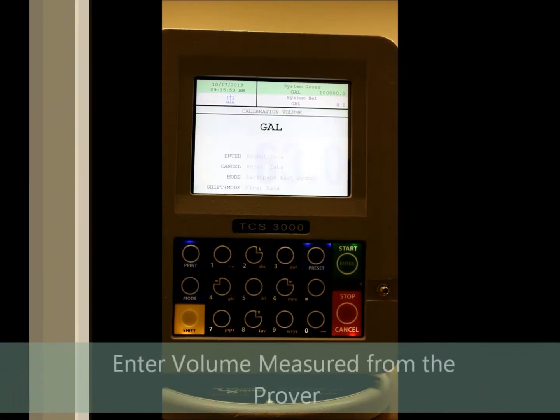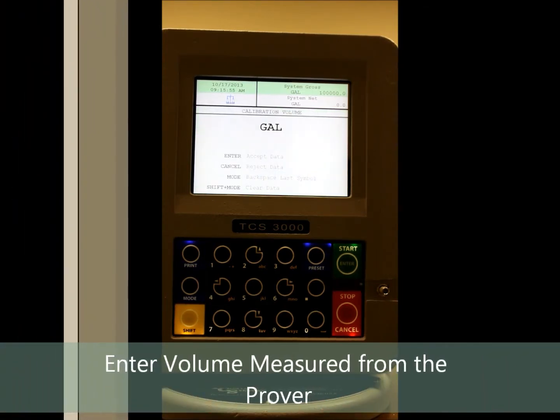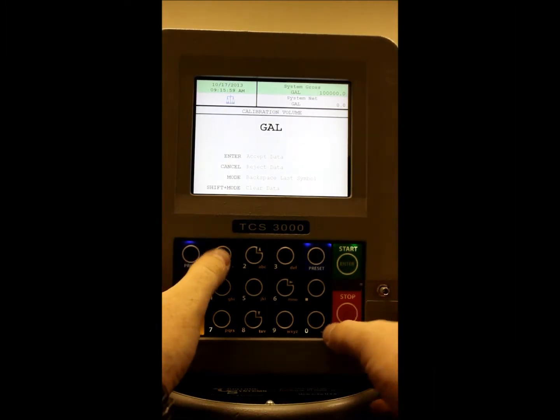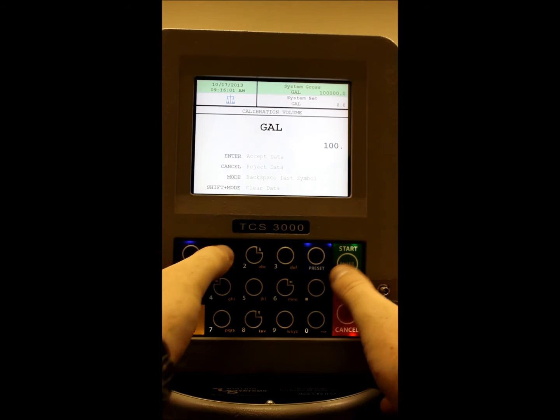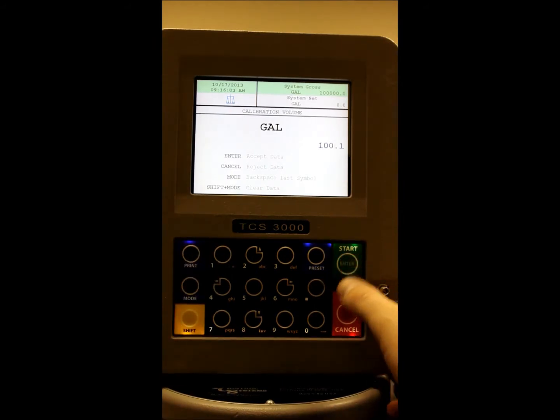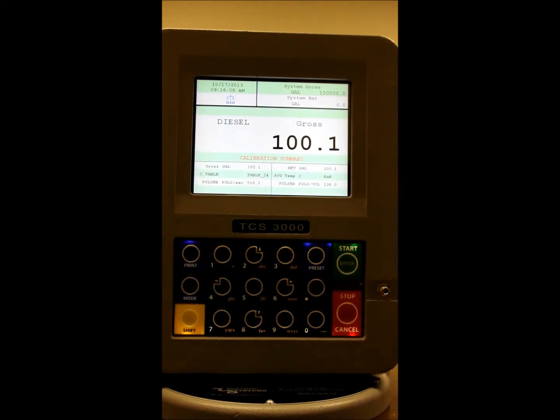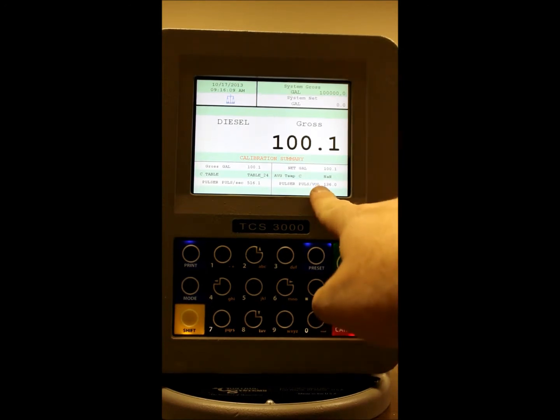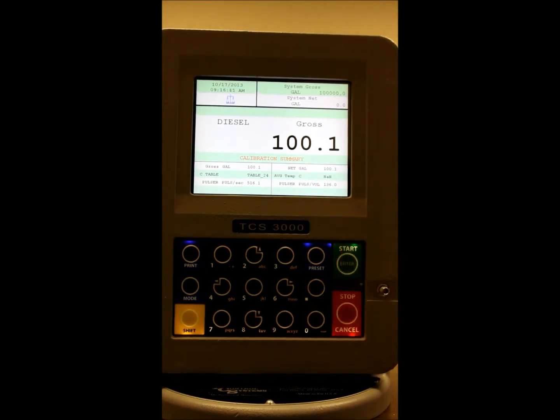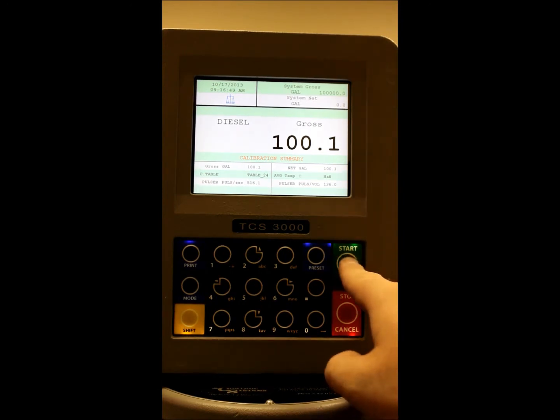When you get your reading from the prover, you'll enter that on the calibration volume screen. So if you ran 100.1 gallons, type in 100.1 and press enter. The TCS3000 will do all of the calculating for you and give you the K factor, which is located at the bottom right of the screen. Once you have reviewed the information on the calibration summary, we'll push the enter key.